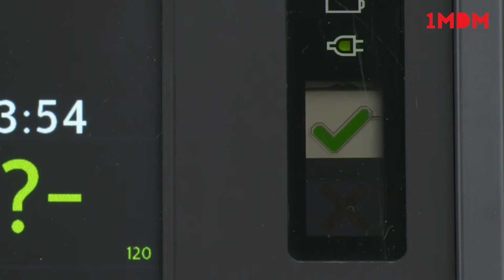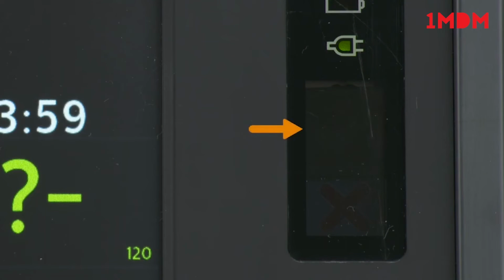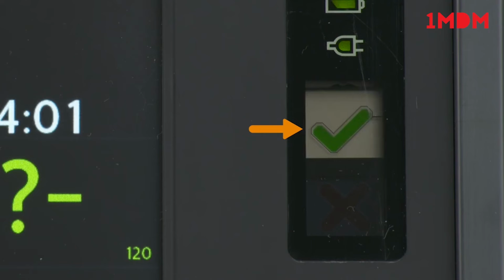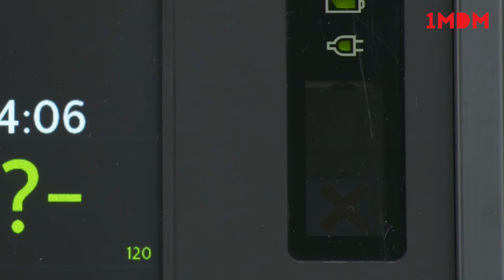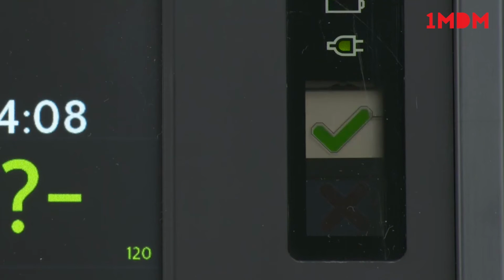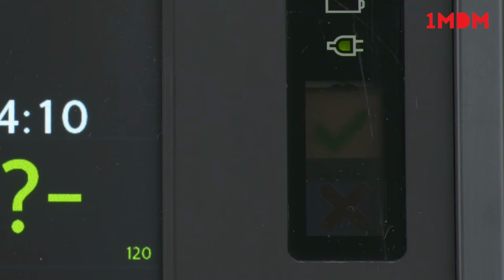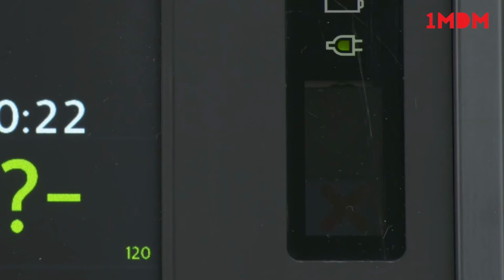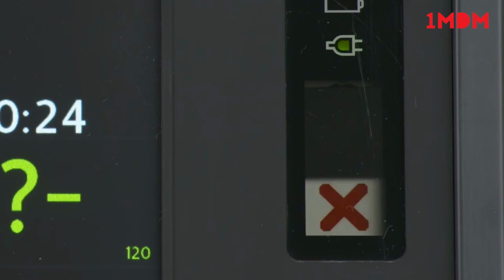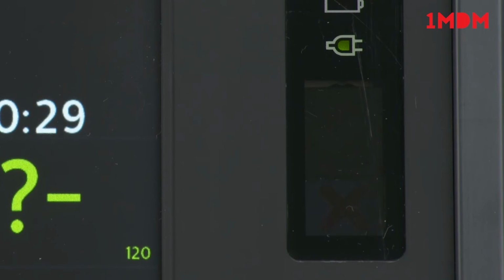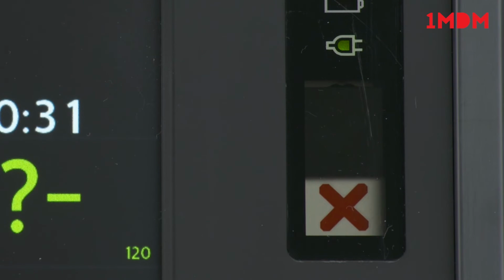To inform you of device readiness, the HeartStart Intrepid is equipped with a Ready for Use, or RFU, indicator. The blinking green checkmark indicates the shock, pacing, and monitoring functions of the device are ready for use, and sufficient battery power is available for device operation. A blinking red X and a periodic audio chirp indicate either a low battery condition or no battery is installed, and the device is running on AC power only.